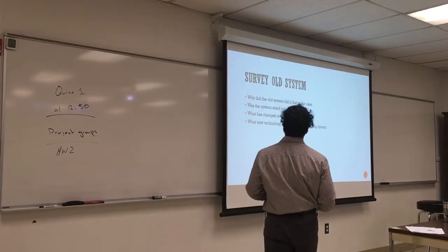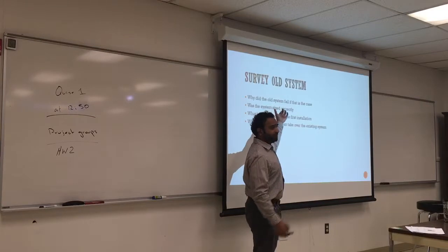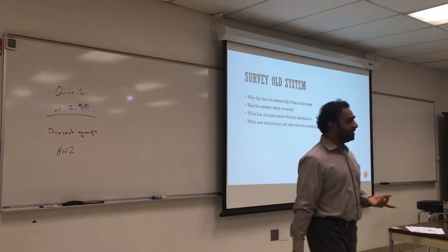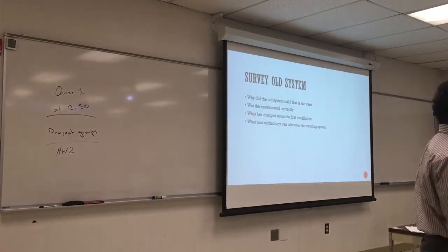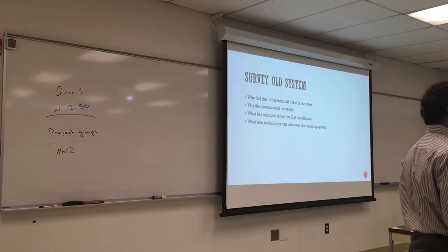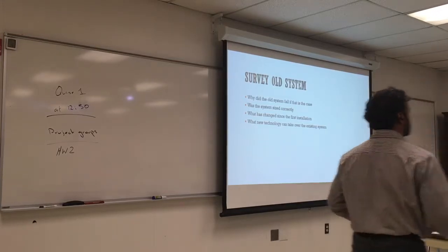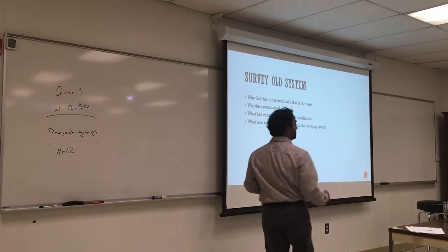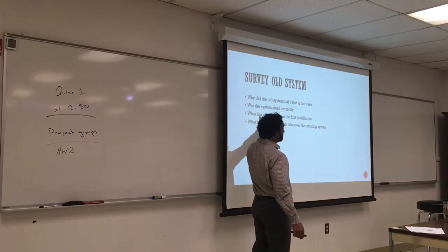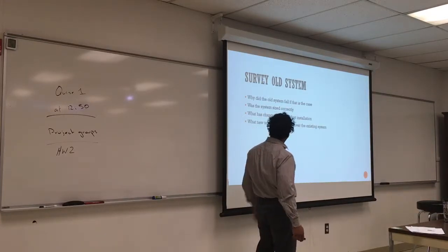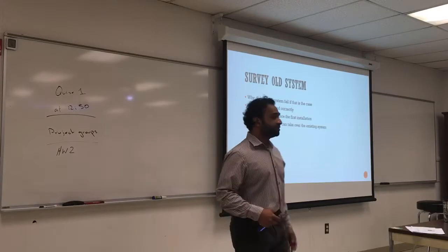Before you start to plan the system, you have to ask yourself a question. Why did the old system fail, and what was the cause? Was it just old age? Was it overworked? Was the ventilation okay? Before you install a new system that's completely the same. Was the system sized correctly? What has changed since the first installation?